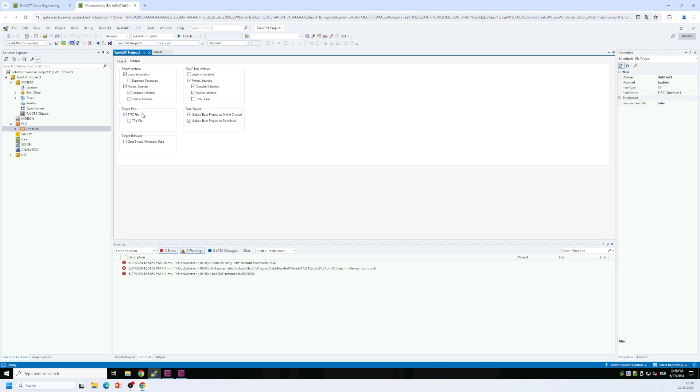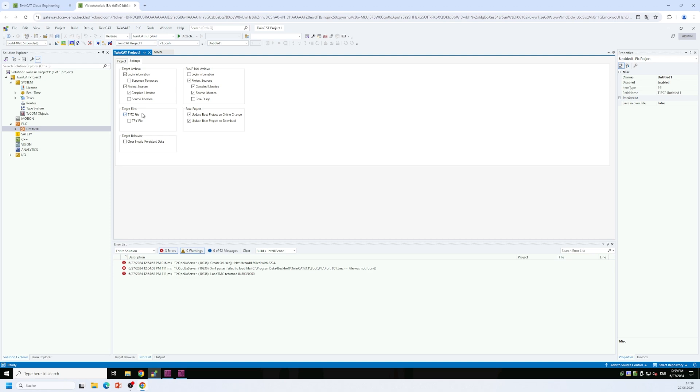What happens in that case is that the TMC file, meaning the symbol file for this PLC project is automatically being downloaded to the target. In our case, it's running on the same system, but it's being downloaded into the runtime. And from there, the TwinCAT OPC UA server will pick up the TMC file in order to browse through its content to see which PLC variables have the PLC attribute been configured so that I need to display this variable in my address space.